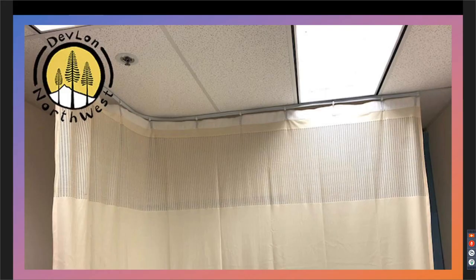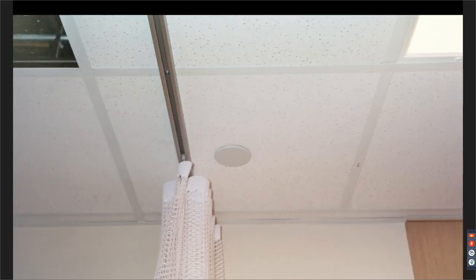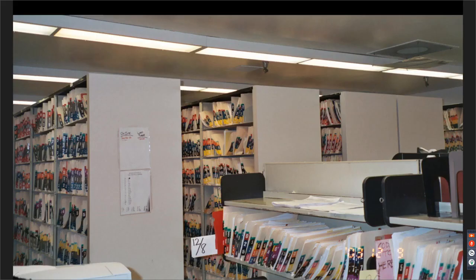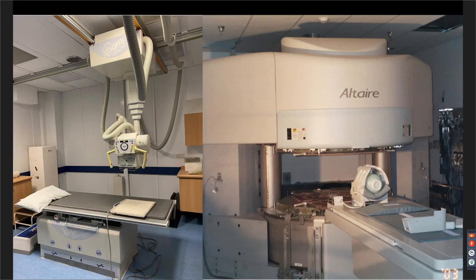Is this sprinkler too close to this cubicle curtain? The answer is actually no, as long as the top 18 inches of the cubicle curtain or the privacy curtain has this mesh style design that you see that has a 1/4 inch space between each of the little cells. What about medical record storage, particularly where these medical records may slide and move and be in different positions that might obstruct sprinkler spray? In radiology clinics, when the pieces are pretty large, do they obstruct sprinkler protection? Or does the gantry slide left and right or back and forth and also obstruct sprinklers? So these are things to please take into account during your design and make sure that the sprinkler system is designed accordingly to avoid problems at the end of the project when you want to get licensed.